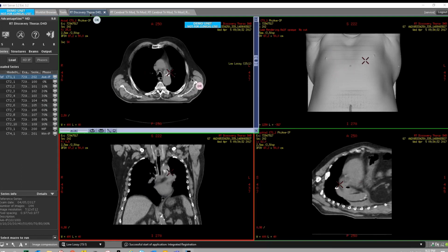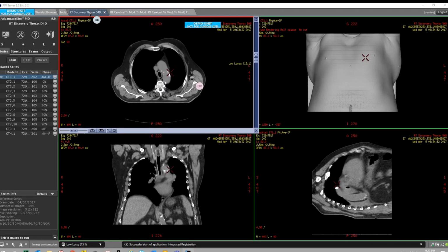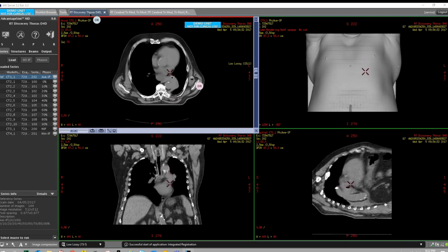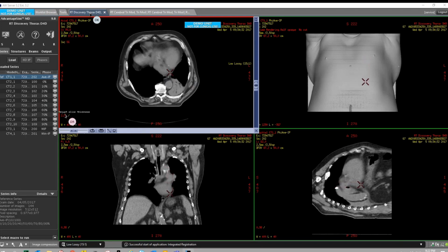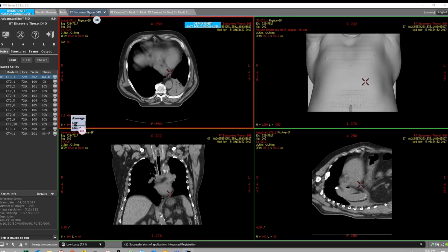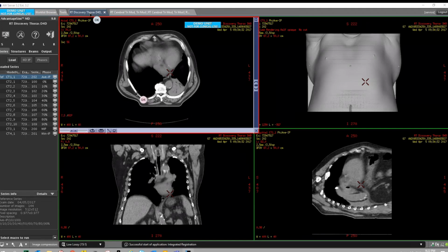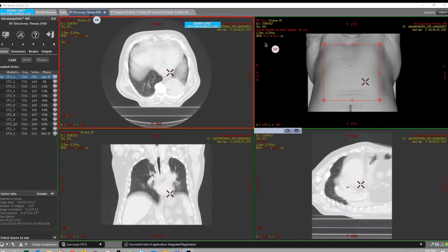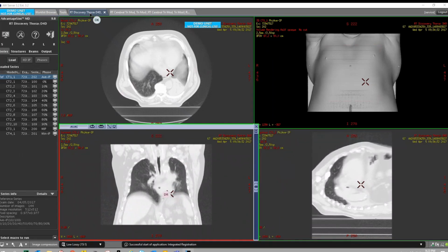We have real-time repositioning to display the native images provided by any CT or MRI. Some display tools are available on the fly to average the morphology or to do maximum intensity projection, for example, and to change the window level from different viewports.